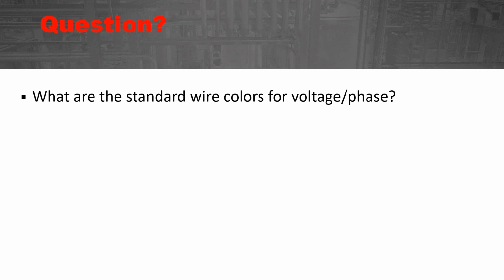If I'm so used to black, red, blue, and white being 120/208 and brown, orange, yellow, and gray being 277/480, if I were to go in a plant and see black, red, blue, I would almost automatically, of course I wouldn't, but I would almost automatically think that that's 120/208, but it is not. So the National Electrical Code gives us standard wire colors, but what we normally think of for 120/208 and 277/480, these are not required colors. Now, the NEC says that if you have two different electrical systems in one enclosure, then you have to mark and label, have information that shows the two different color coding systems.